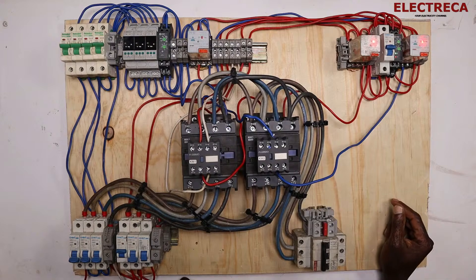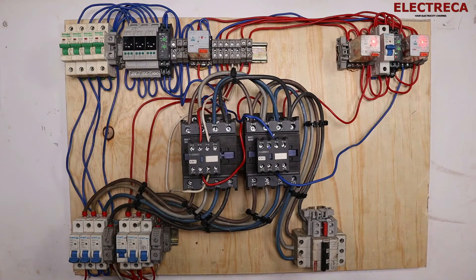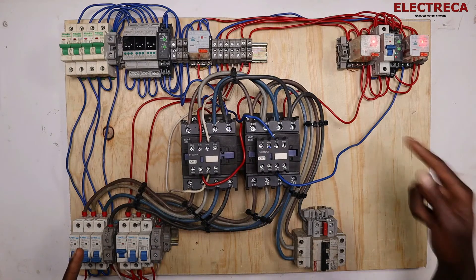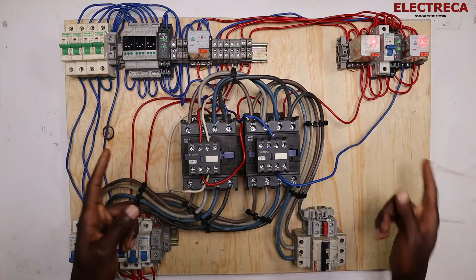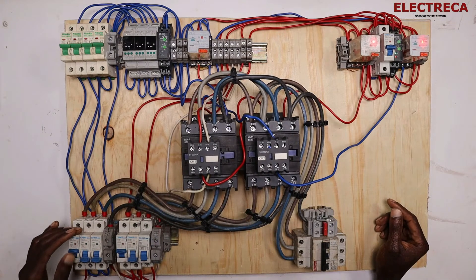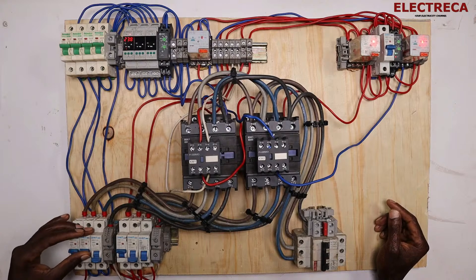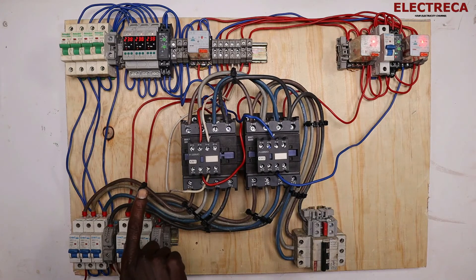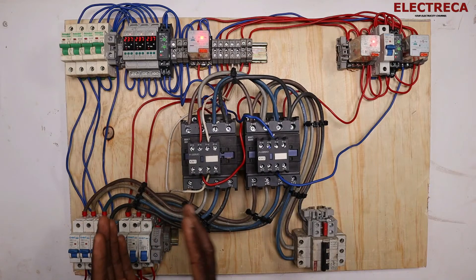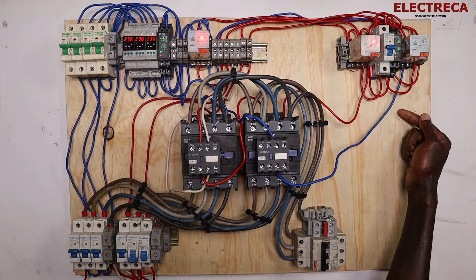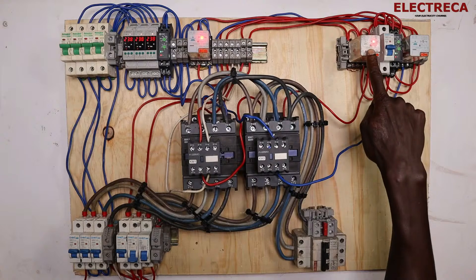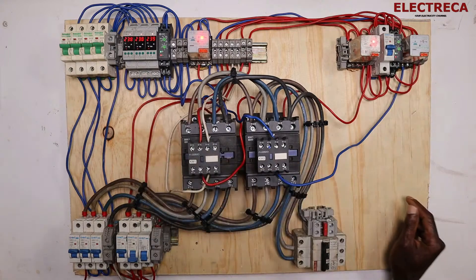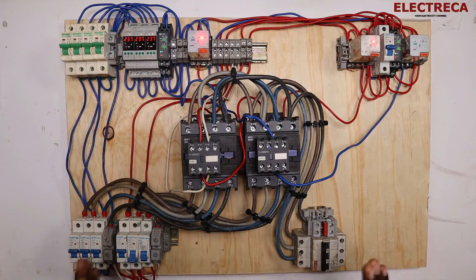One thing you have to understand is priority. The mains is the priority in this configuration. So if the mains resumes while the generator is supplying the load, the mains circuit will override the generator circuit and the mains will take over. All three comparators are on, the timer has run, and the mains has taken over. That's how this circuit operates.